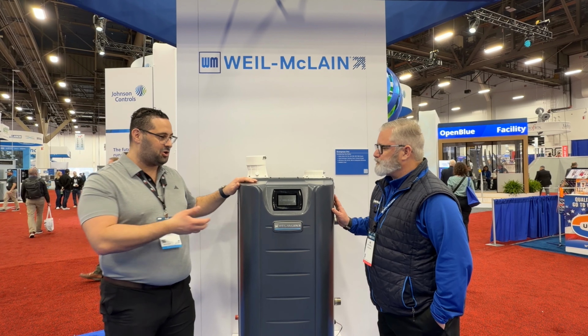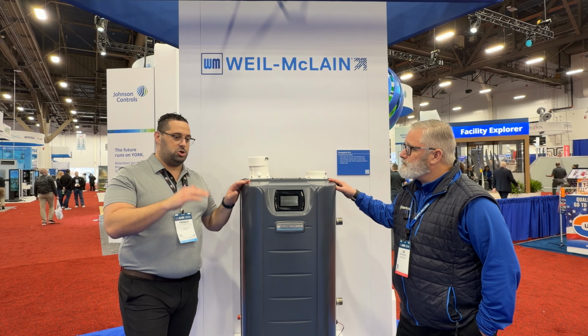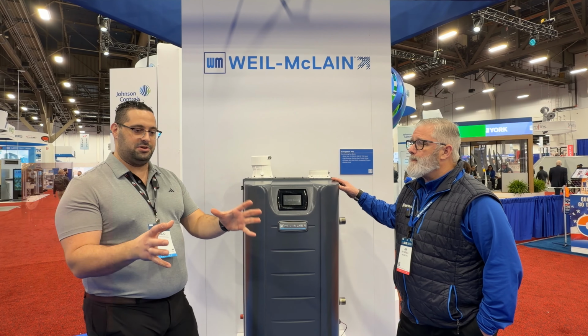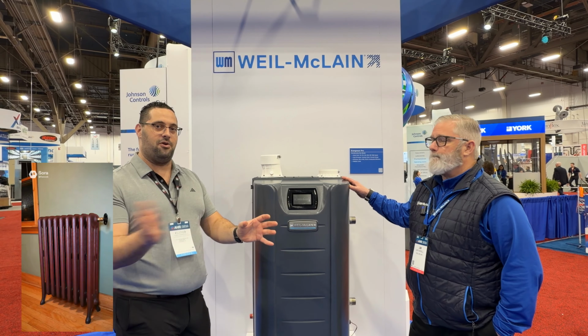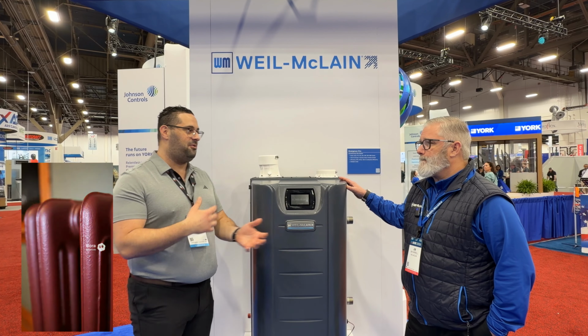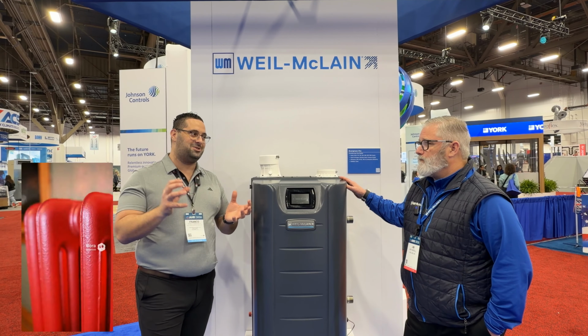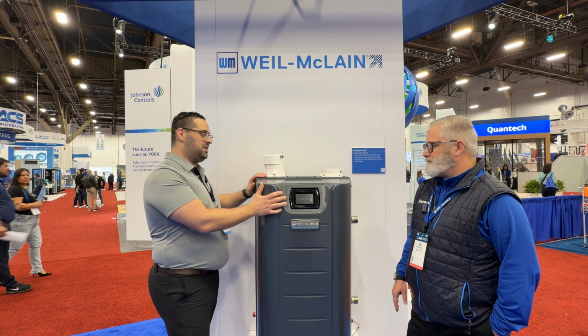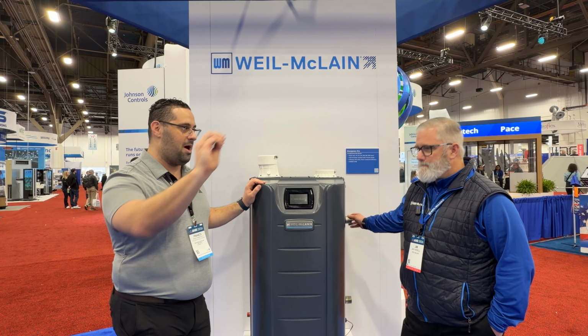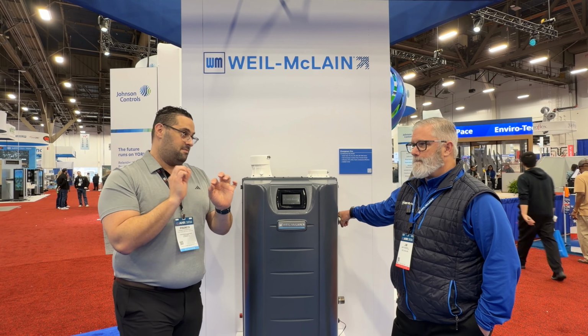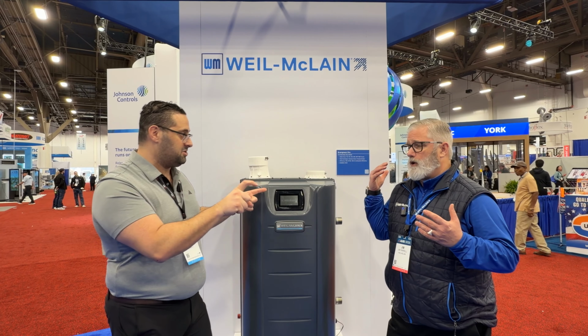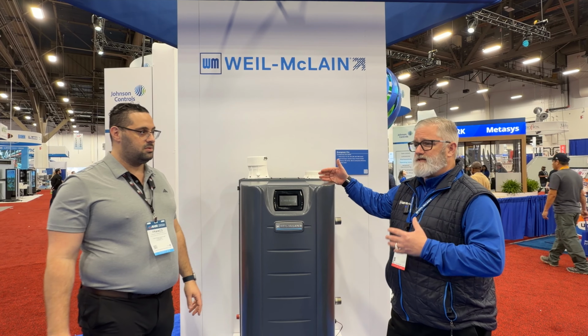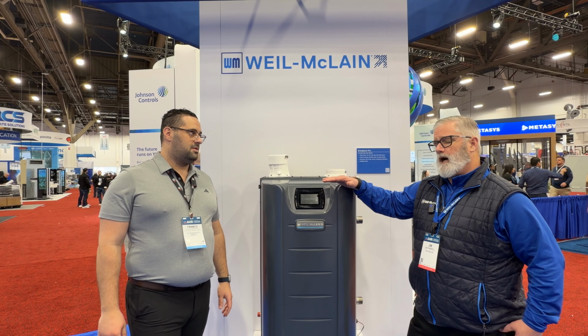Yep. Helps a little bit, but when it comes to comfort and modulating, I know it saves money, but what I always say is, correct me if you agree, modulating means this boiler, instead of most people's traditional boilers which are single stage, either on and off. So in spring and fall when you need just a little bit of heat, that's where the boiler lacks, it's too hot, it feels like a sauna. Right. This thing can adjust the amount of heat it puts into the water and how much hot water it circulates in basically 1% increments based on outdoor temperature and whatever the homeowner set the thermostat to, right? Correct. Outdoor temperature is what drives this boiler, and it provides comfort heat inside the home.